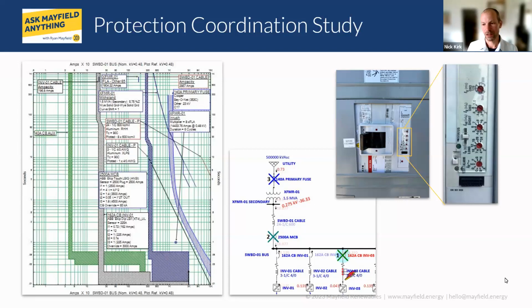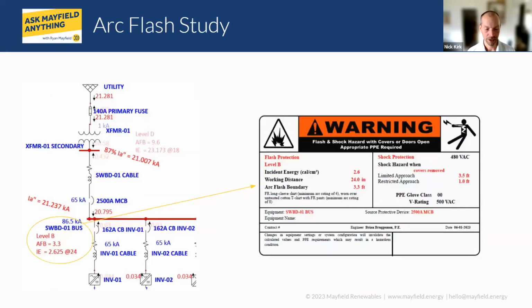Yeah, and then the last study we ran here was the Arc Flash. Once we have this model built, then we can run the Arc Flash analysis, and that produces all the information that would go on the Arc Flash labels, such as the incident energy, working distance, arc flash boundary, and required PPE for that hazard.